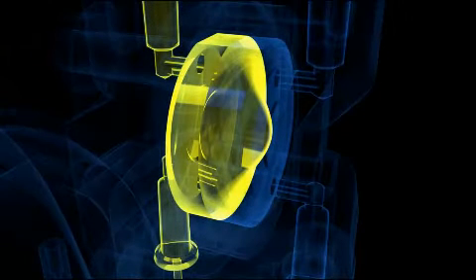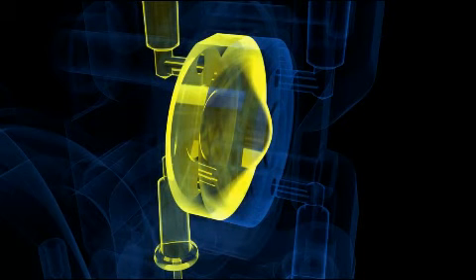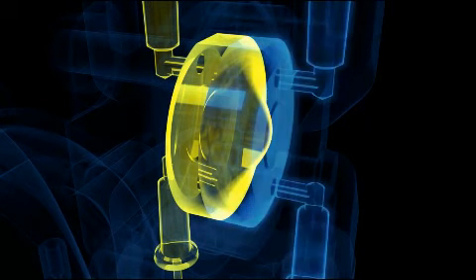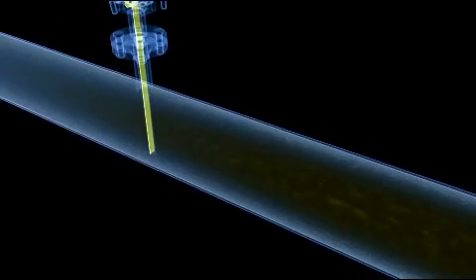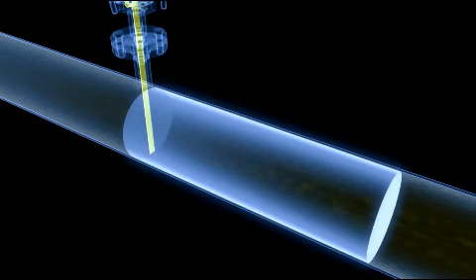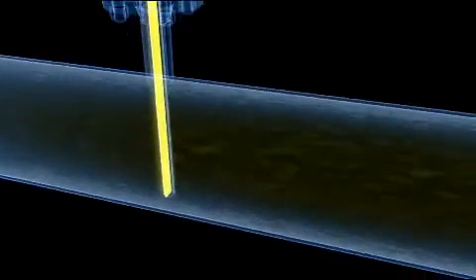As a result, different values are detected in the pressure chambers of the sensor. Higher pressure against the flow and constant pressure on the rear of the Pitot tube. This pressure difference is a direct measure for the flow velocity and thus the mass and volume flow in the pipe. The higher the flow velocity, and therefore the dynamic pressure, the greater the differential pressure measured.